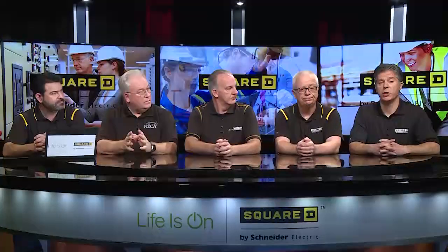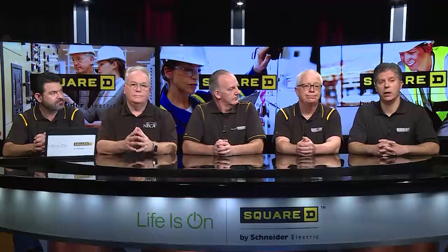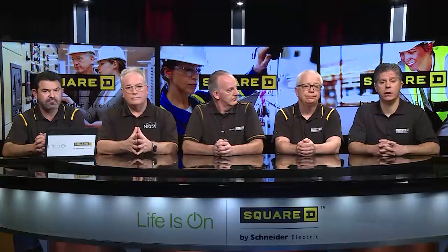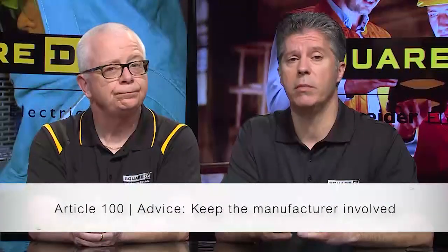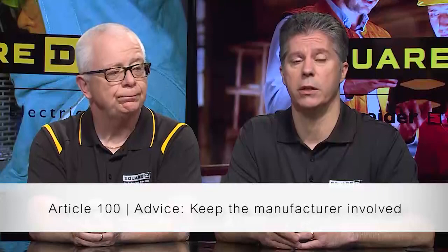That's a great point, because product standards get updated for safety as well as the NEC. So there are new requirements the standard would have in place for some of these products, and that's an important factor as you reevaluate a reconditioned piece of equipment. The other piece is to keep the manufacturer involved in your reconditioning decision process. Many times the actions of reconditioning can cause more damage to the equipment, and that's why you'll find the basis of some products where the NEC says it should not be reconditioned. In any case, refer to the manufacturer's instructions.